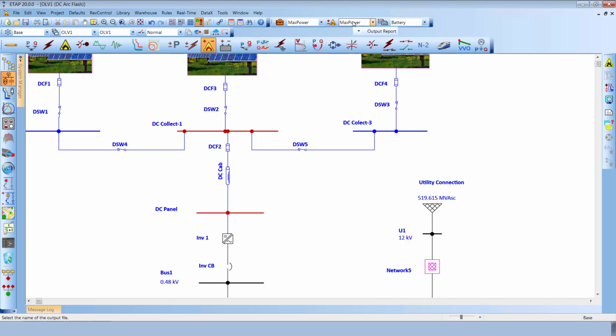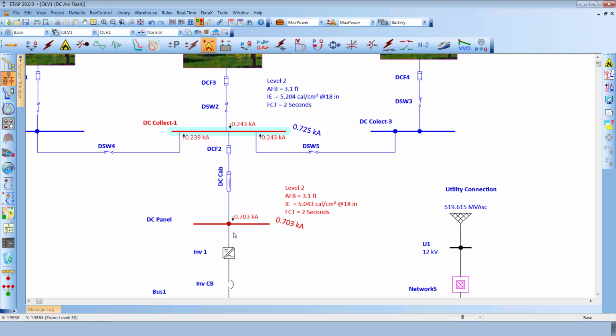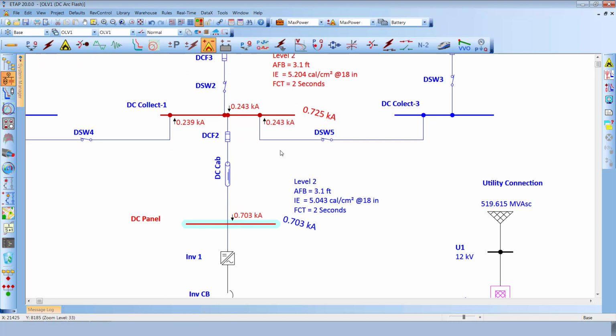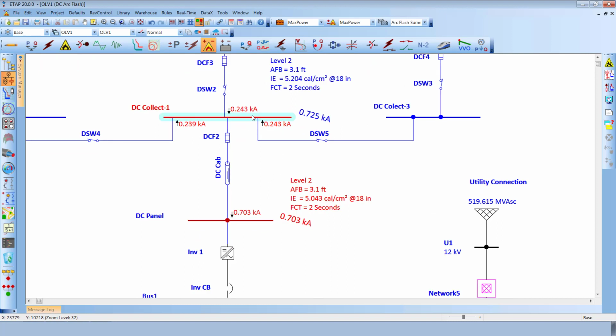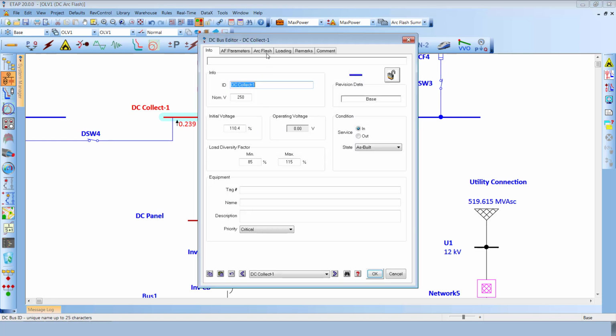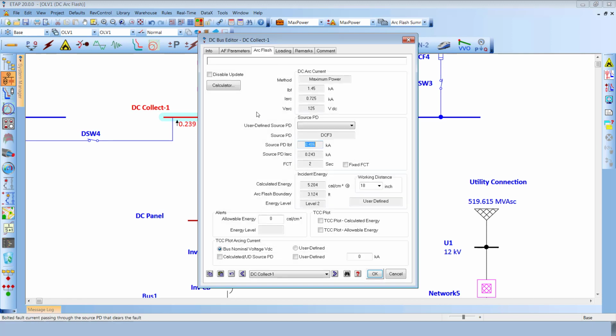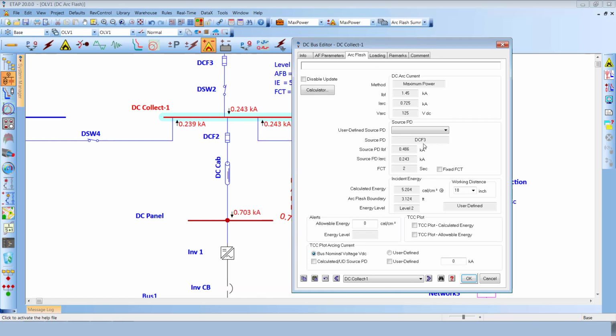To begin with, let us first run the maximum power method case and observe the results on the DC collect 1 and the DC panel respectively. Maximum power method calculation for the DC combiner box, which in this case is the DC collect 1, is summarized in the bus arc flash page. The total incident energy calculated in this location for a given working distance is based on the operating time of the source protective device DCF3, which is operating at 0.243 kiloamps that is seen in the source path.